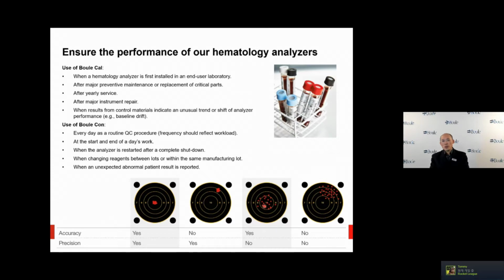Either it is due to pre-analytical factors, blood sample handling, old sample, anticoagulant problem, or due to the precision measurement of volume in the instrument. So in this case, we need to solve the precision problem before we can check the accuracy. And if the precision is good and accuracy is not, then we come to the scenario that the instrument needs calibration. Here the calibrator blood comes into play.